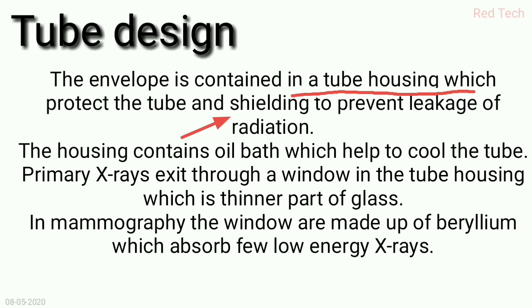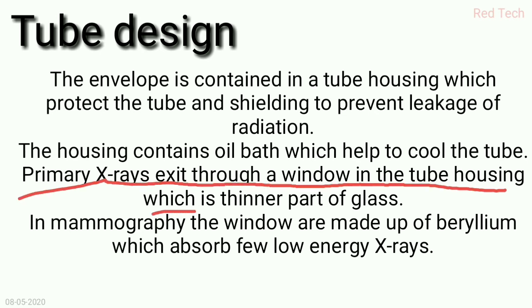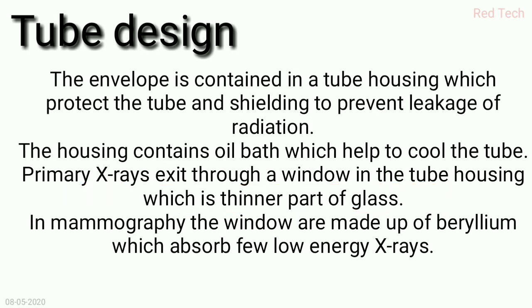The envelope is contained within a tube housing which protects the tube, provides shielding, and prevents leakage of radiation. To prevent radiation leakage, the housing contains an oil bath which also helps to cool the tube. Primary x-rays exit through a window — a thin glass window present in the tube housing.